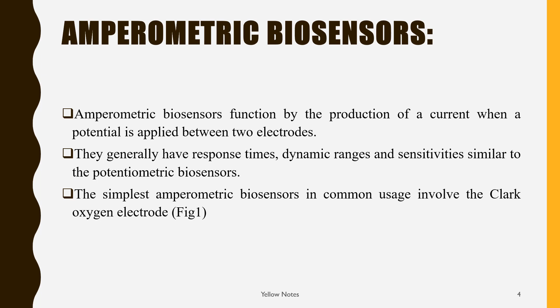Amperometric biosensors. Amperometric biosensors function by the production of a current when a potential is applied between two electrodes. They generally have response times, dynamic ranges, and sensitivities that are similar to the potentiometric biosensor. The simplest amperometric biosensor in common usage involves the Clark oxygen electrode.